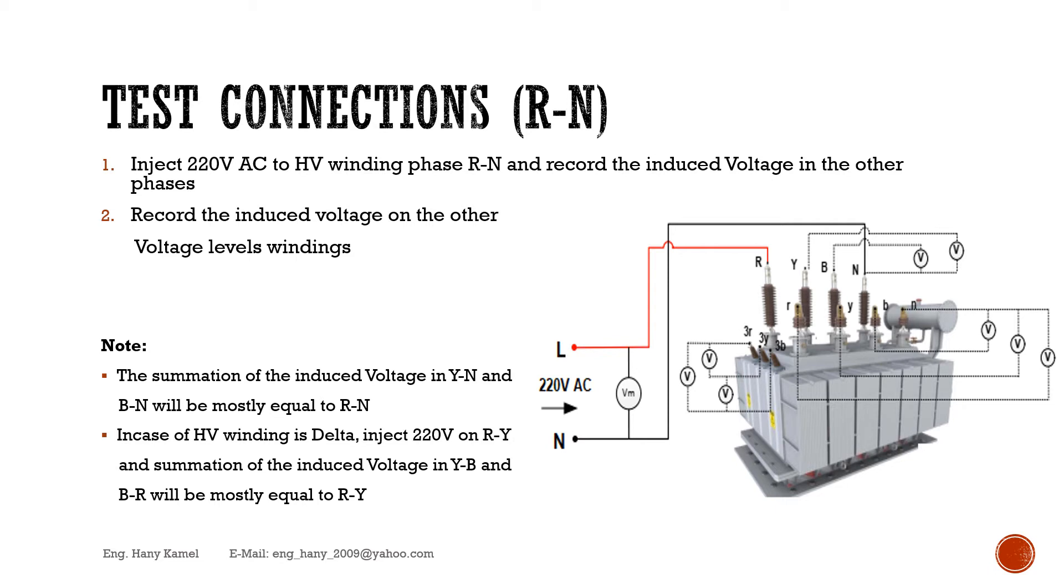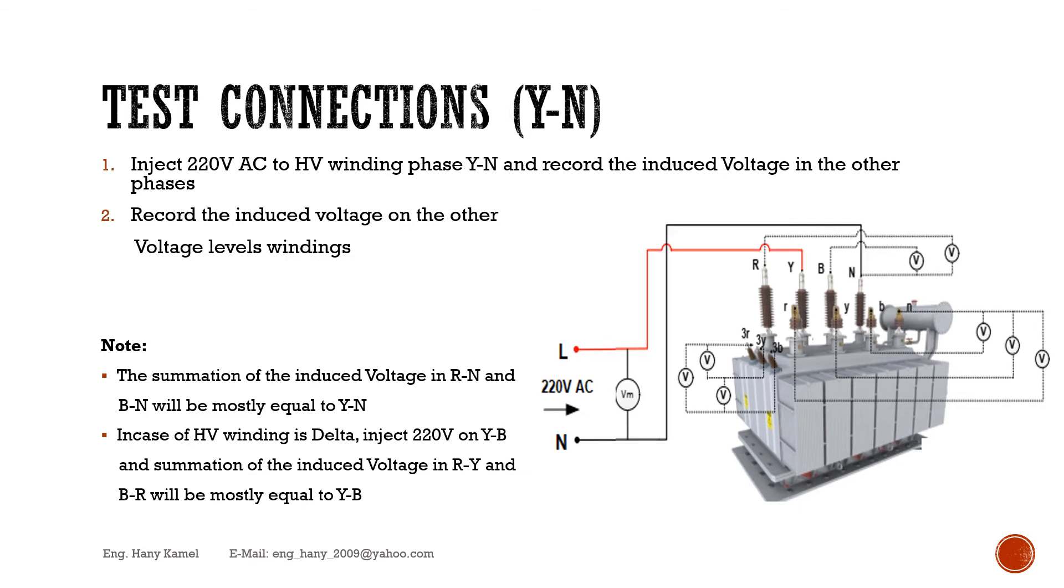In case of HV winding is delta, inject 220 volts on R-Y and summation of the induced voltage in Y-B and B-R will be mostly equal to R-Y.